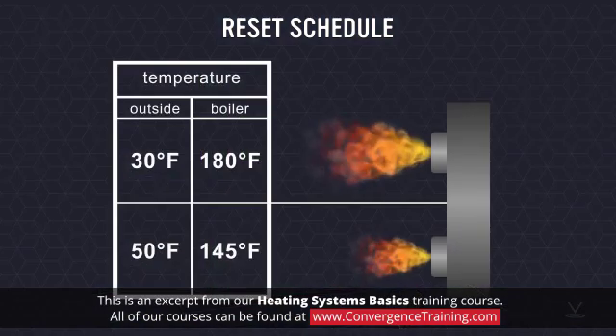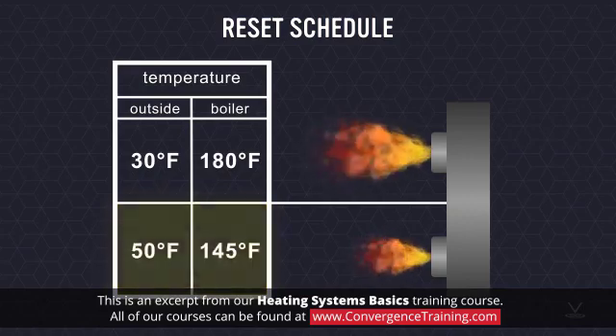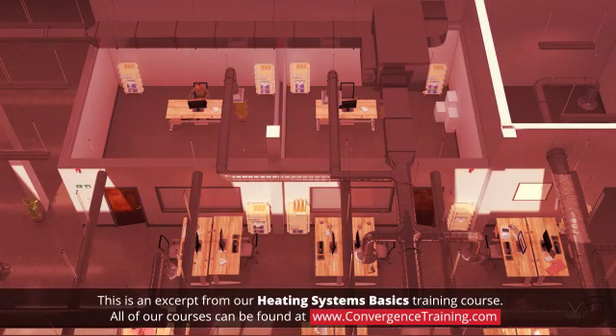As the outside air temperature rises, the hot water supply temperature is lowered. Not only does this reset save energy, but it also minimizes overheating of conditioned spaces.